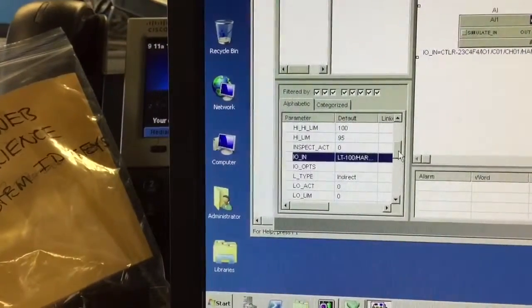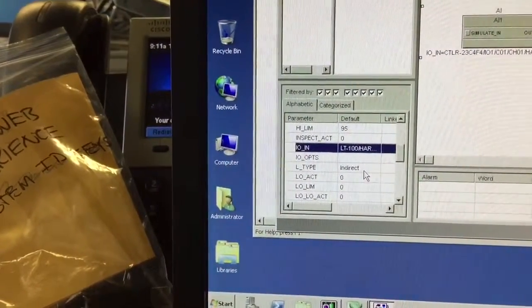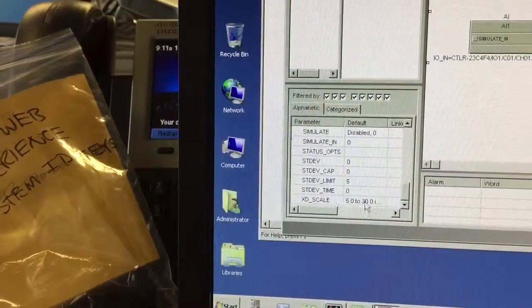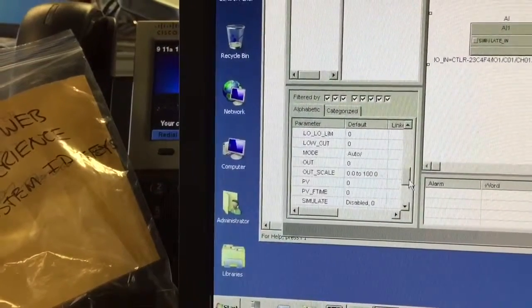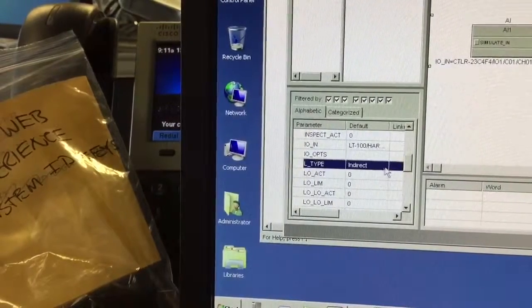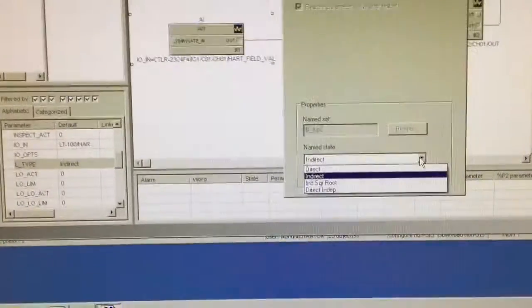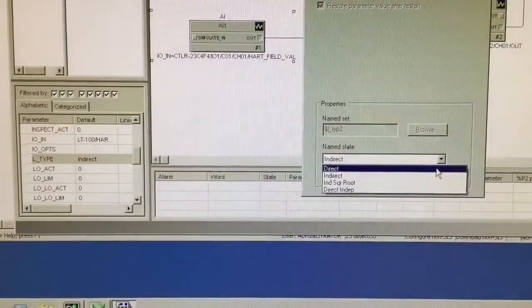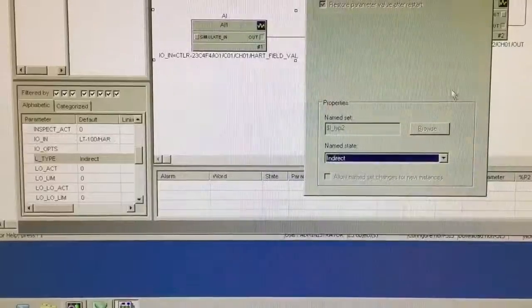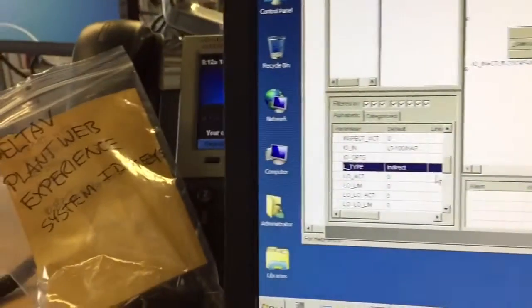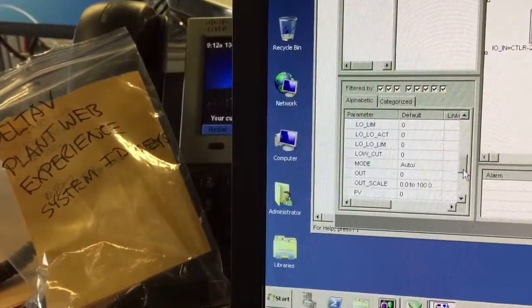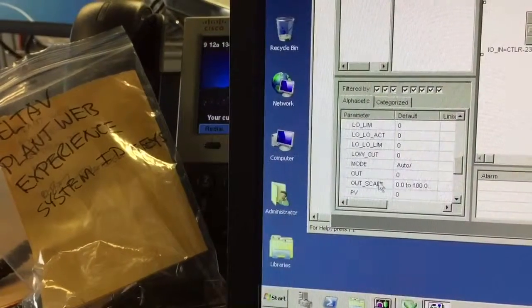So that is how you set it up and configure it. And then when you're working with the HART field valve parameter, if you're doing indirect scaling like we just did in our demo, the XD scale will be written to the device. Whereas if you are doing direct, or you're just pushing the data right through, or you can select direct right here, if you're doing direct then the outscale would be written to the transmitter. So our outscale parameter right here.